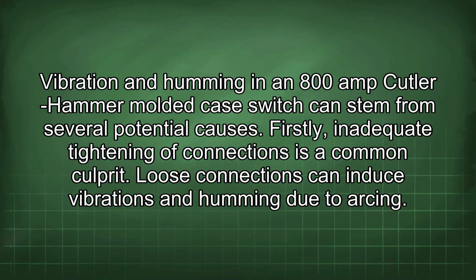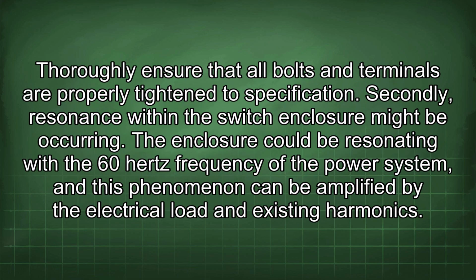Vibration and humming in an 800 amp Cutler-Hammer molded case switch can stem from several potential causes. Firstly, inadequate tightening of connections is a common culprit. Loose connections can induce vibrations and humming due to arcing. Thoroughly ensure that all bolts and terminals are properly tightened to specification.